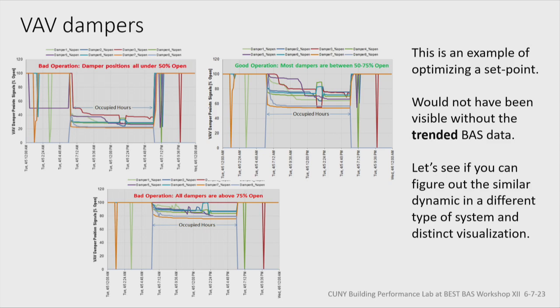How many trunks are coming off of that duct system? What else is happening in the scenario? Is it heating? Is it cooling? I need to bring the full picture, full circle, in order to have an accurate and informed way of presenting the systematic problem, not a parts problem, especially when it's just percent open. We don't have other variables available. And I think the more variables you have to present a system problem in regards to a building automation issue that you're trying to educate somebody about is probably the most effective way to start developing that mentality. And I guess that's my constructive criticism of the scenario.